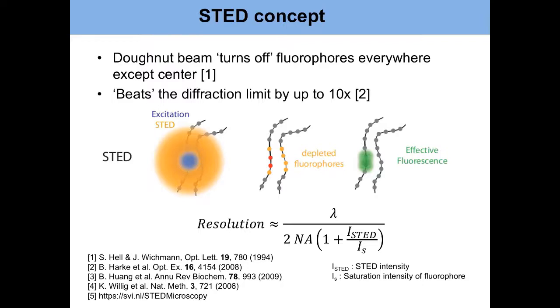So what happens is you come in and you're exciting your fluorescent molecules, but with the STED beam you get stimulated emission. So where the fluorophores see this laser, they basically emit a photon of that specific wavelength, and then using a filter you can block that, and you only get the effective fluorescence from the very center where there's no intensity in that STED mode.